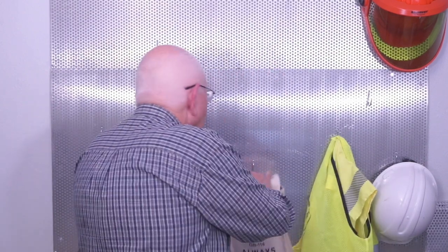Not enough information. In fact, Subpart K gives you some general statements about protecting the worker, which is good, from shock. Really nothing at all about arc flash. And it says, hey, if you're going to go out there and use something like a jackhammer, and you're not sure if there's any cables underground or underneath that concrete, whatever you're doing, get yourself some rubber gloves. This is the requirement, and it says wear some voltage-rated rubber gloves in order to protect yourself while you're out there using that jackhammer. Well, that's a good idea. And there are requirements, as we know, in the testing and inspection and all of that in 70E.